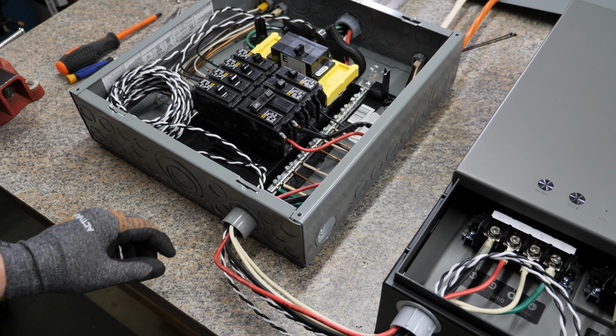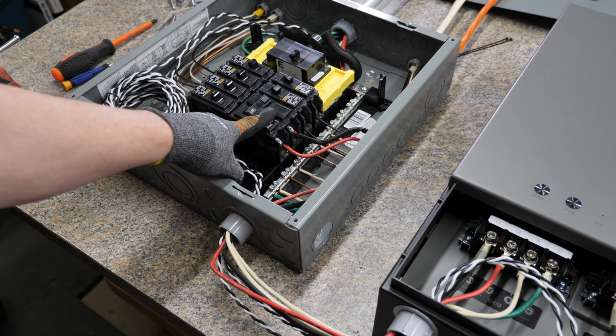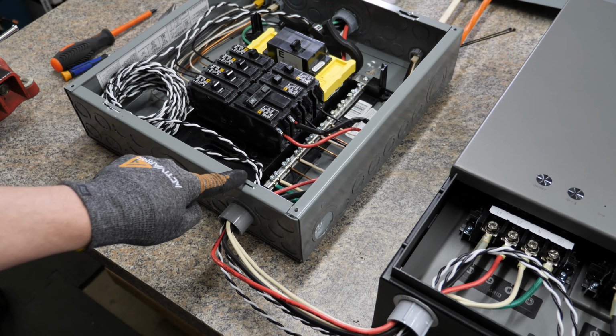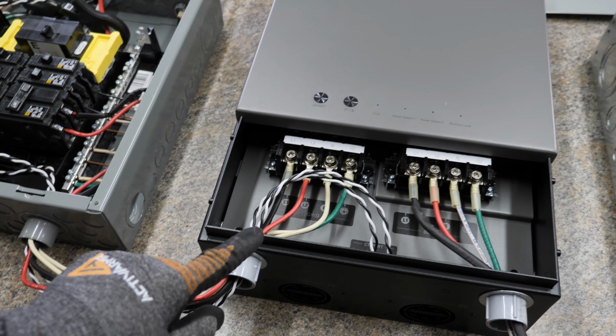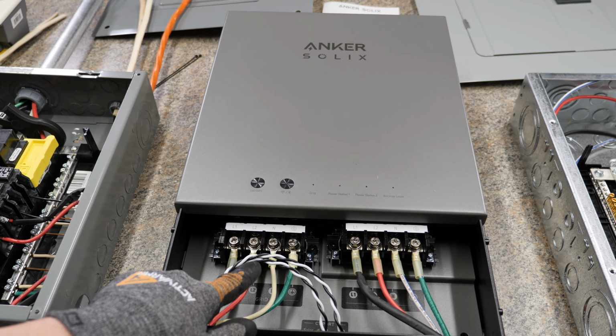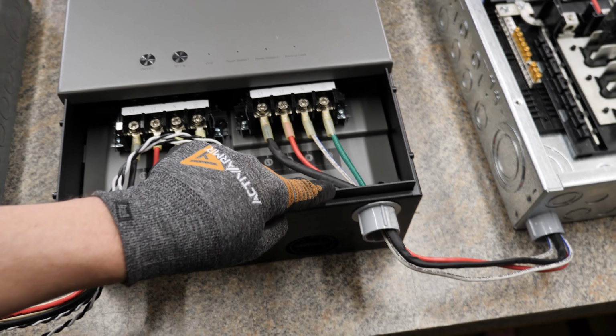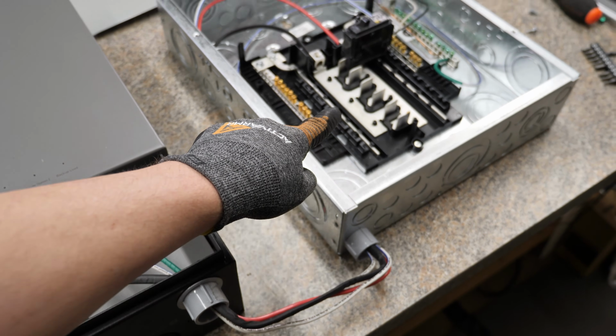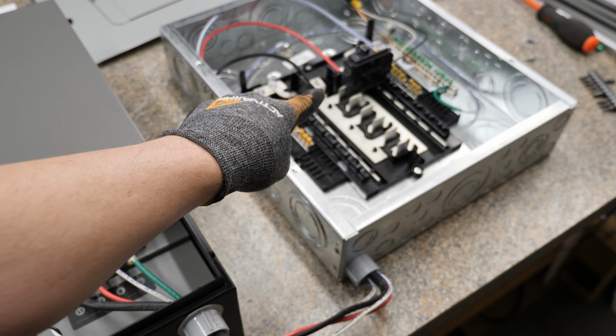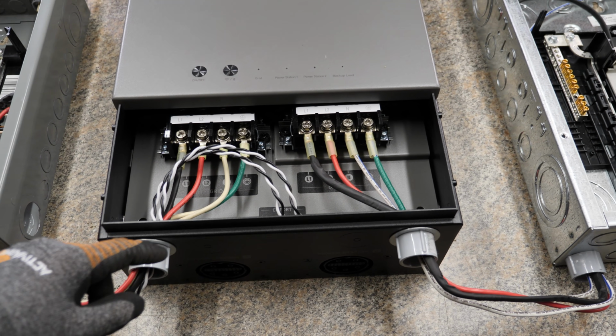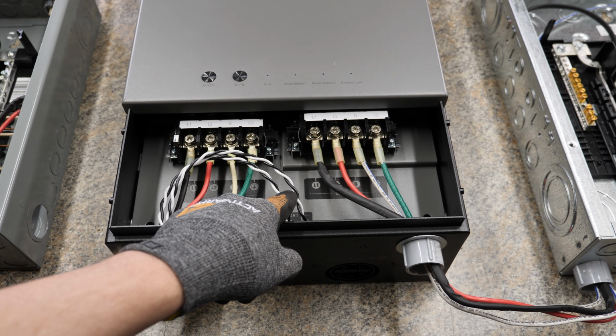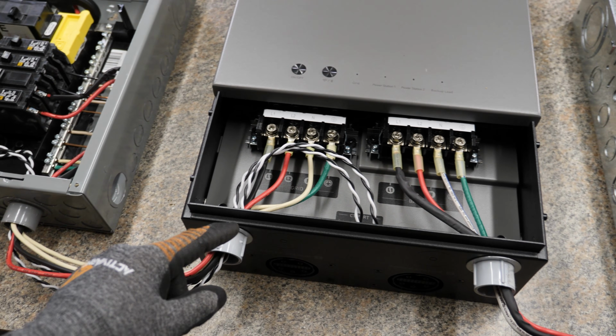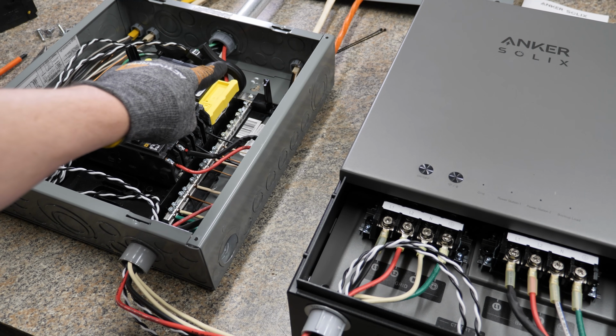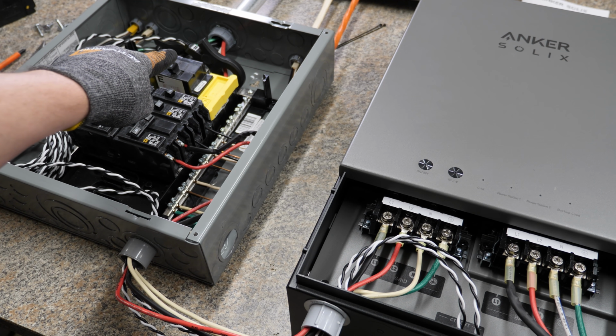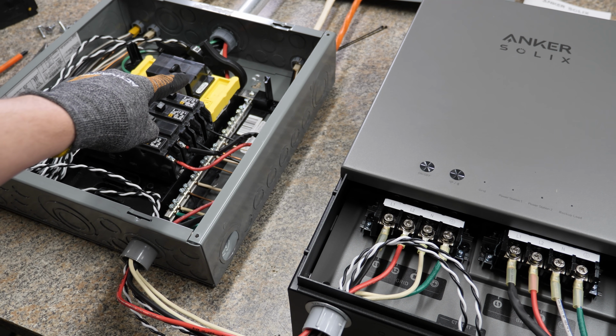All right, so we got everything connected. Main power comes from this circuit breaker right here. We wrap around, go over, and then into the home power panel, and then out of the home power panel again, into the sub panel right over here. And back over here, you can see we have our two CT clamps, L1 and L2, which are connected or clamped up there at the top of the main panel, L1, L2.